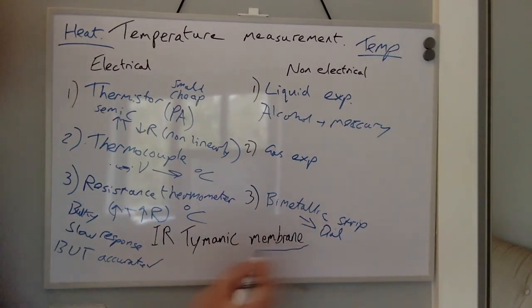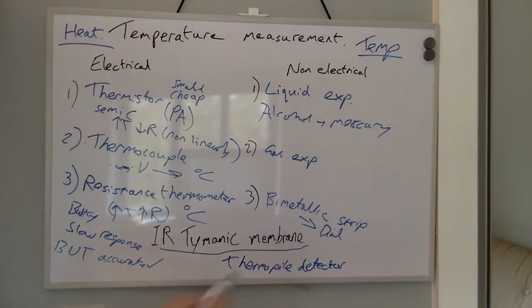And for infrared tympanic membrane thermometers, all objects emit electromagnetic radiation. The tympanic membrane has a thermopile detector, and this is made up of multiple thermocouples.